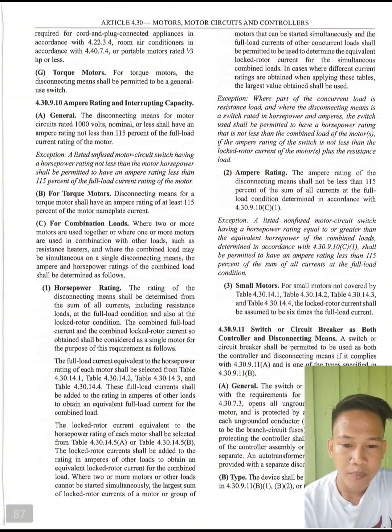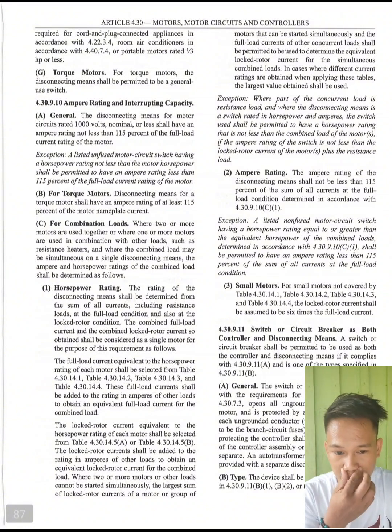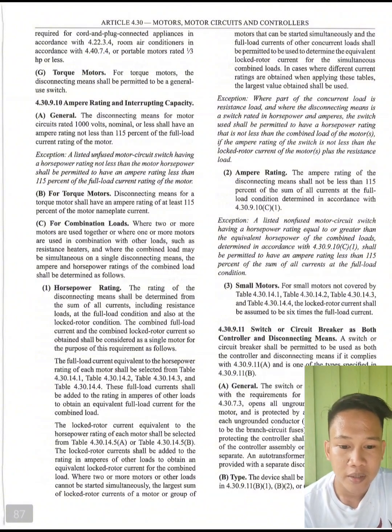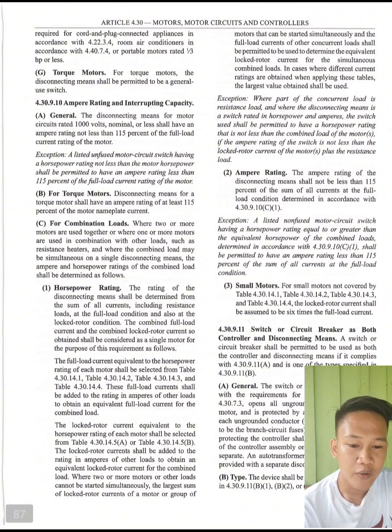Next, we have 430.110, ampere rating and interrupting capacity. So, general. The disconnecting means for motor circuits rated 1000 volts nominal or less shall have an ampere rating not less than 115 percent of the full-load current rating of the motor. Now, you have an exception. The exception is a listed unfused motor circuit switch having a horsepower rating not less than the motor horsepower shall be permitted to have an ampere rating less than 115 percent of the full-load current rating of the motor. B. For torque motors, the disconnecting means for a torque motor shall have an ampere rating of at least 115 percent of the motor nameplate current.